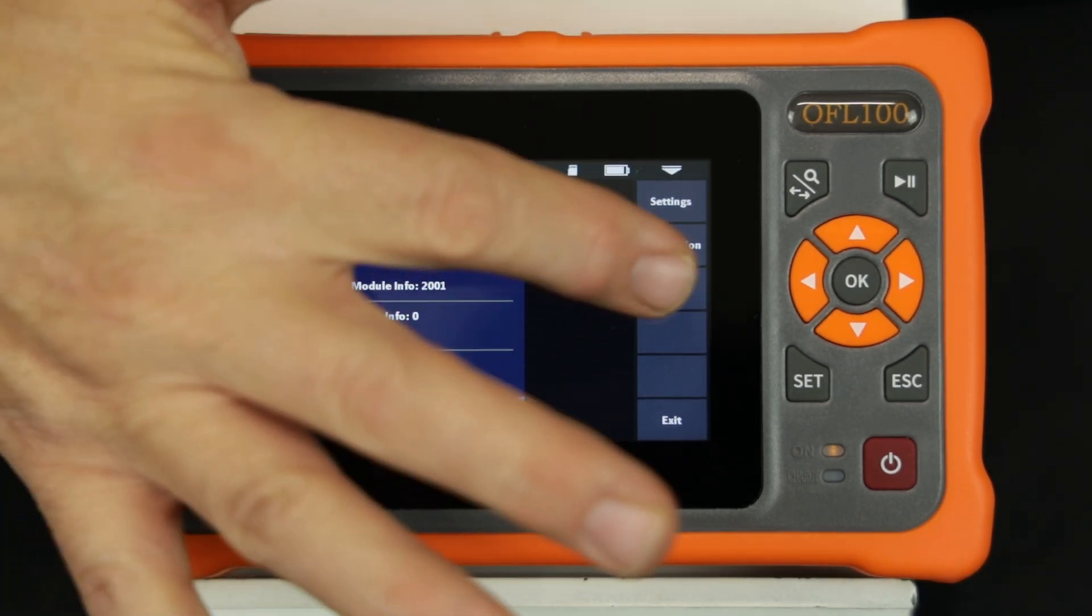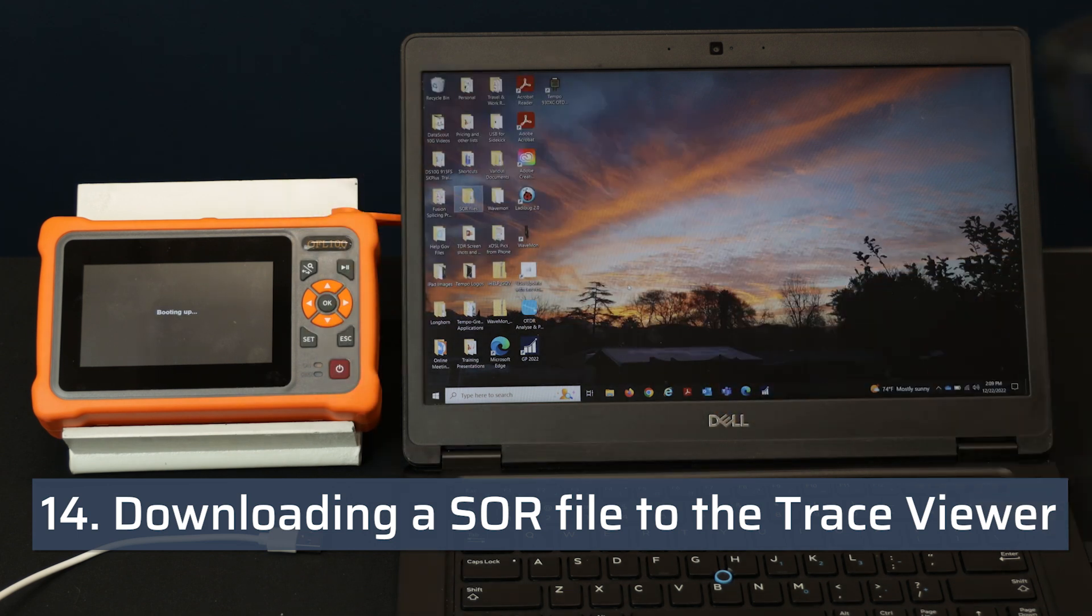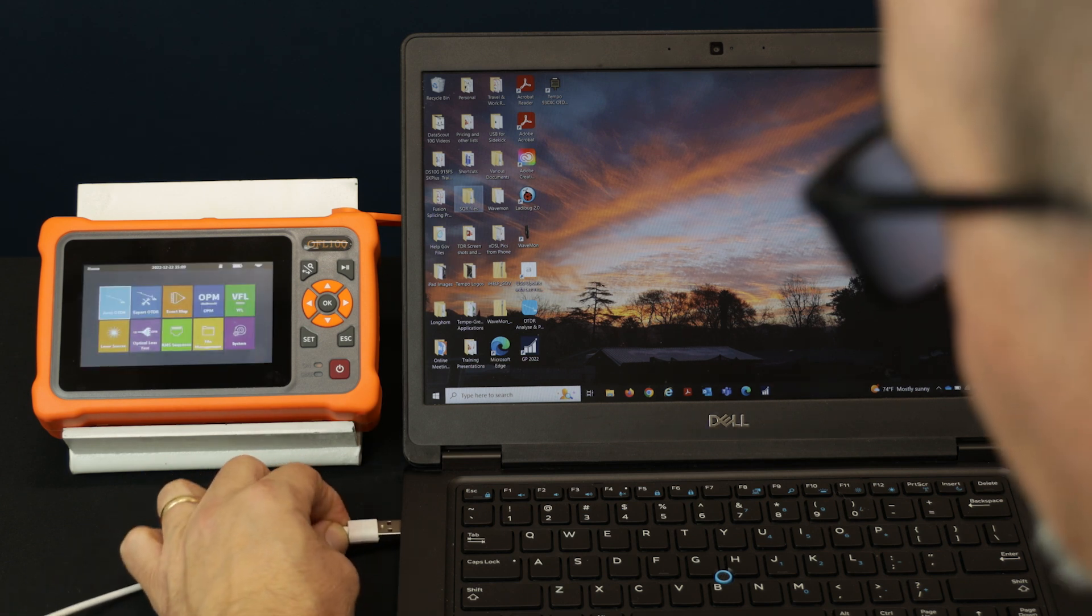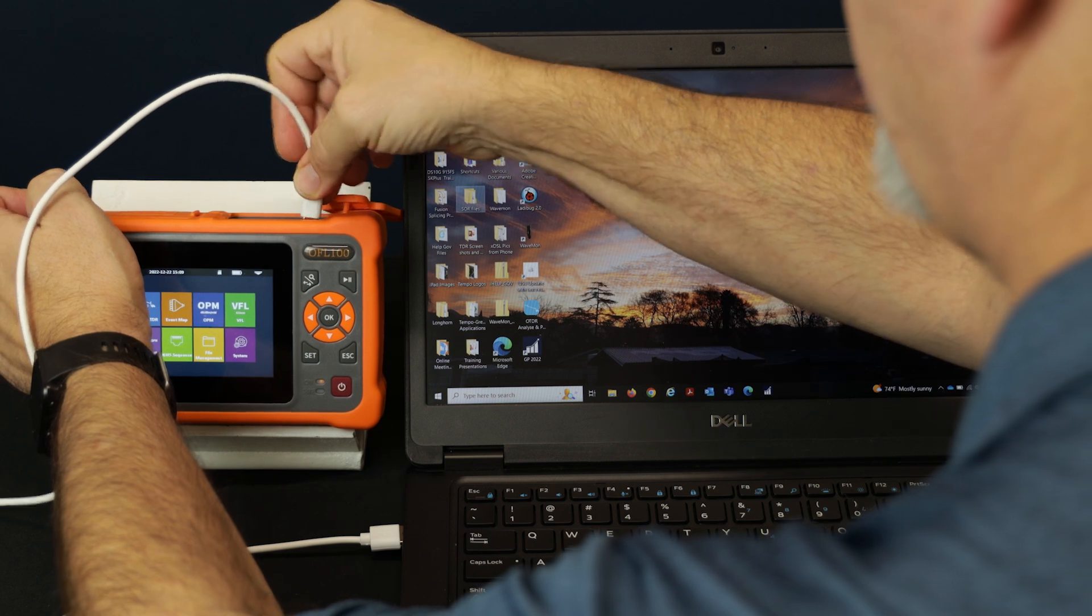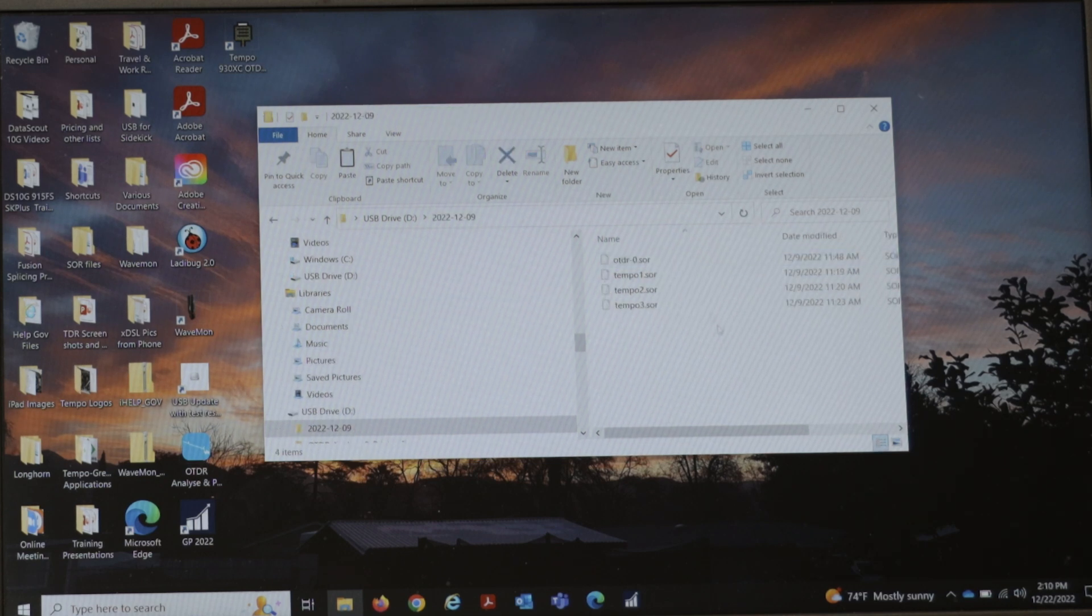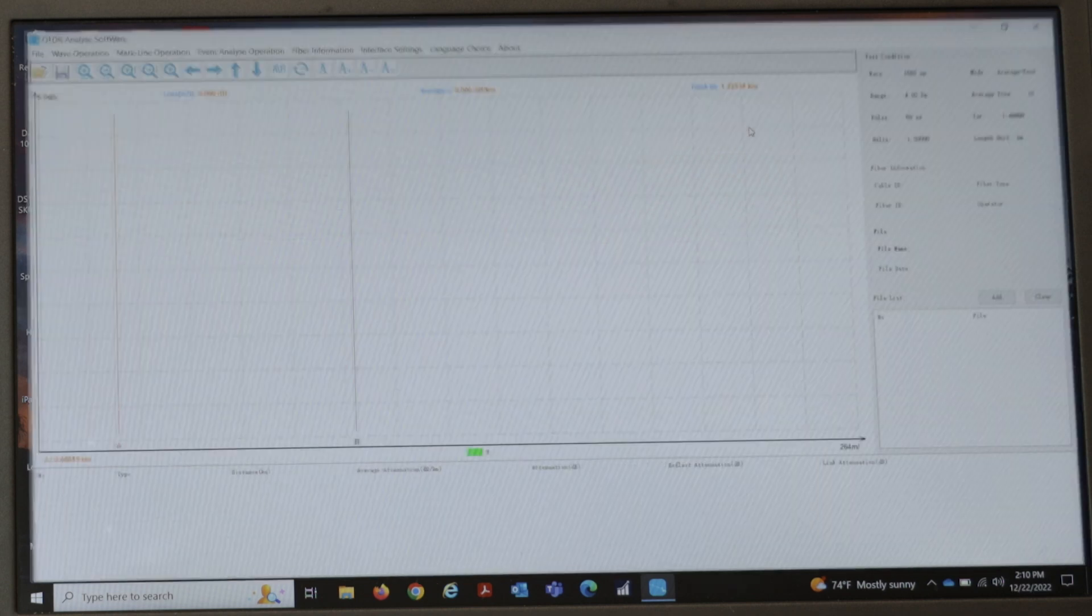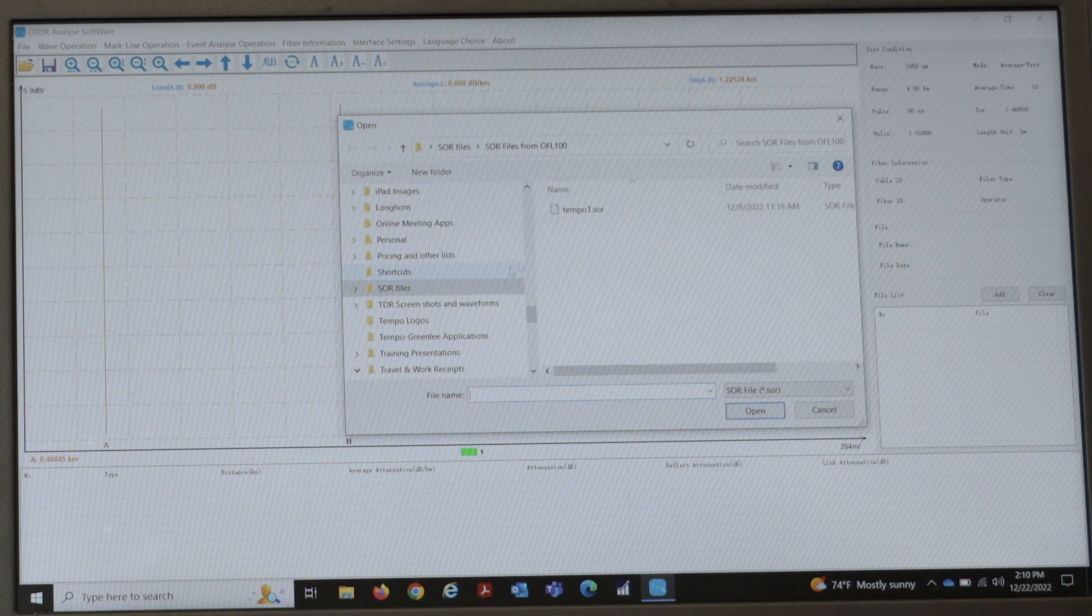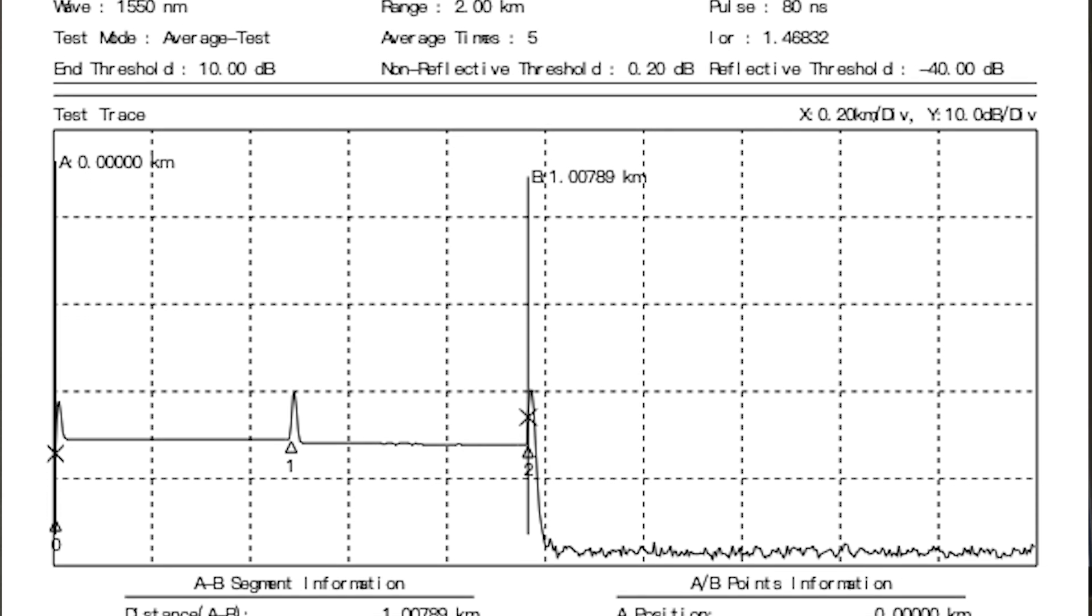The saved files on the OFL100 can be exported to a Windows computer for use in the Trace Viewer. Turn on the OFL100 and connect the OFL100 to the computer using the supplied USB cable. The USB acknowledgement tone should be heard. Navigate within Windows Explorer to the saved SOR files. Copy the desired file to your computer. Open the Trace Viewer and use the folder open icon to open the SOR file saved on the computer. The saved file will then be displayed. The technician can then view and augment the data to create a closeout report.